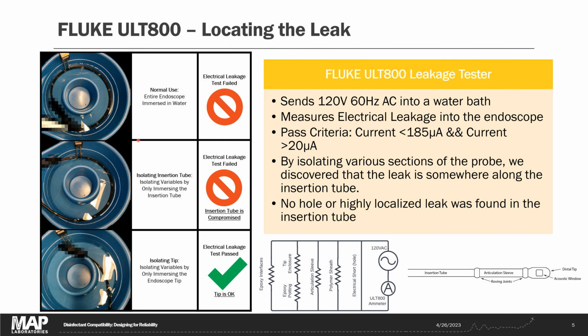By isolating various sections of the probe, we can eliminate some of these electrical leakage pathways and figure out where the problem actually is. So for instance here, we've immersed only the tip of the endoscope and we passed the electrical leakage test at that point. So that allows us to eliminate all of these materials and interfaces as potential leakage pathways. By eliminating the articulation sleeve, these roving joints, the tip material, and the acoustic window, we basically leave only this polymer sheath of the insertion tube and potential holes as the electrical leakage pathway.